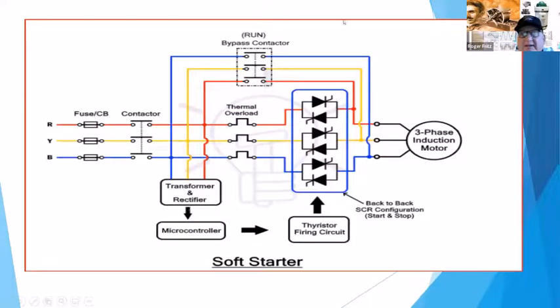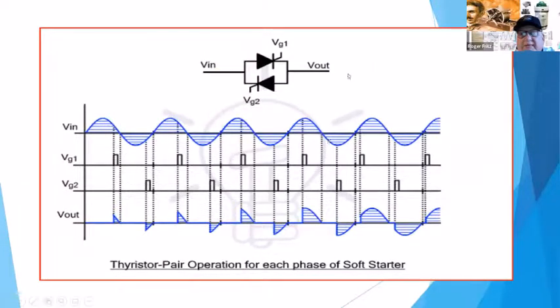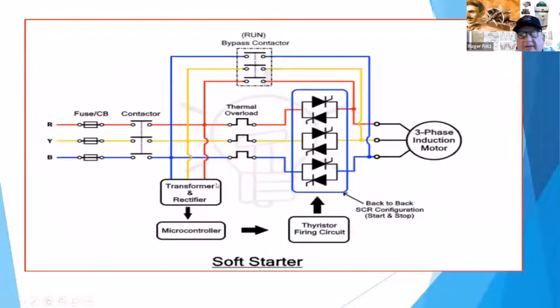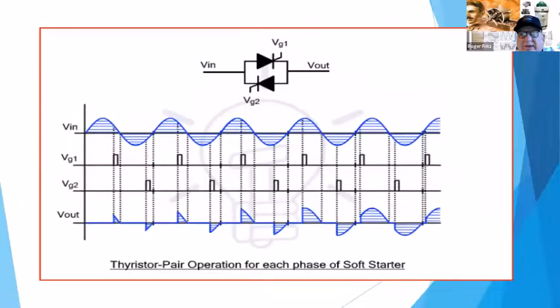So this is a diagram of pretty much the standard soft starter, where they normally have a contactor or a disconnect switch ahead of it, and it goes directly in. It's got a thermal overload built into it. And then it has these 3 sets of SCRs that are basically just switching and turning the waveform, again, back to that waveform that's coming off of the generator. They can control when they're turning it on and when they're turning it off. They're a very cost-effective technology today. Everybody tends to move right away to VFDs, which I think there's a little bit of an over push on, because there are some disadvantages to variable frequency drives that we're going to talk about a little bit further into the discussion.